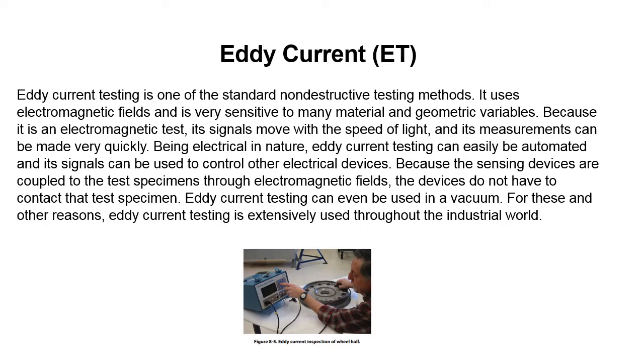Eddy Current Testing is one of the standard non-destructive testing methods. It uses electromagnetic fields and is very sensitive to many material and geometric variables. Because it is an electromagnetic test, its signals move with the speed of light and its measurements can be made very quickly. Being electrical in nature, Eddy Current Testing can easily be automated and its signals can be used to control other electrical devices. Because the sensing devices are coupled to the test specimens through electromagnetic fields, the devices do not have to contact the test specimen. Eddy Current Testing can even be used in a vacuum.